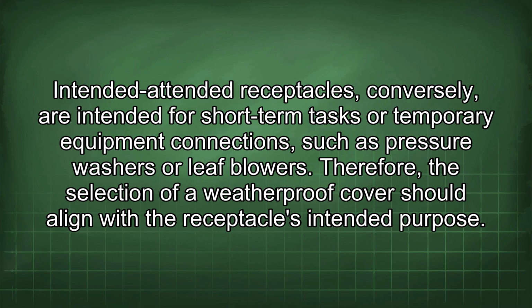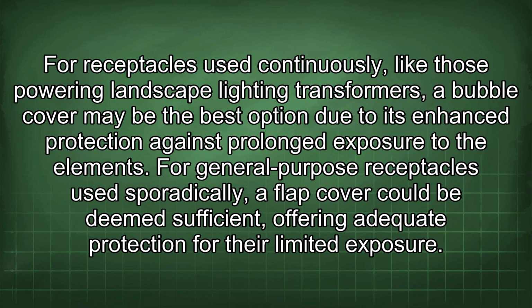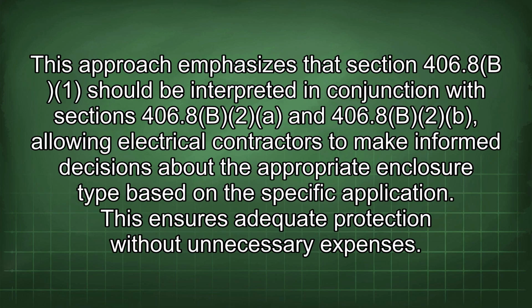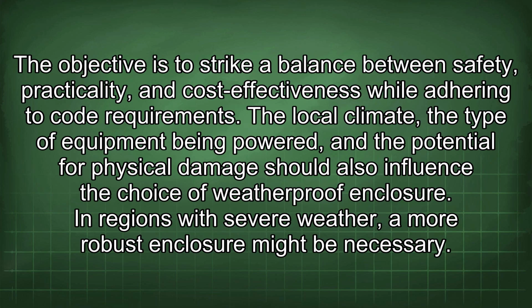Therefore, the selection of a weatherproof cover should align with the receptacle's intended purpose. For receptacles used continuously, like those powering landscape lighting transformers, a bubble cover may be the best option due to its enhanced protection against prolonged exposure to the elements. For general-purpose receptacles used sporadically, a flap cover could be deemed sufficient, offering adequate protection for their limited exposure. This approach emphasizes that Section 406.8(B)(1) should be interpreted in conjunction with Sections 406.8(B)(2)(a) and 406.8(B)(2)(b), allowing electrical contractors to make informed decisions about the appropriate enclosure type based on the specific application. This ensures adequate protection without unnecessary expenses. The objective is to strike a balance between safety, practicality, and cost-effectiveness while adhering to code requirements.